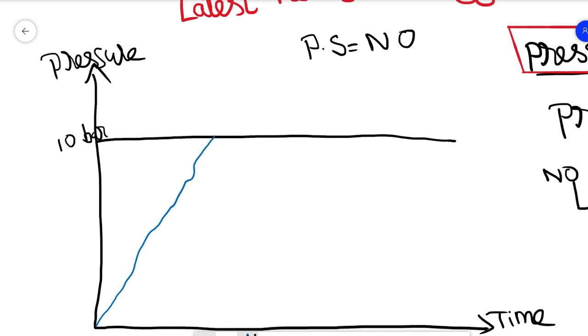During the gradual increment of pressure, the pressure switch doesn't sense any pressure and it remains in its original contact, NO contact, normally open contact. When the process pressure achieved 10 bar pressure, the pressure switch changes its contact to NC, that is normally close contact.